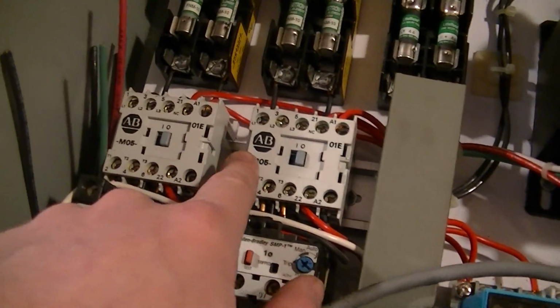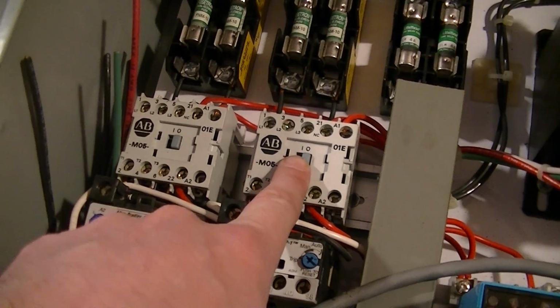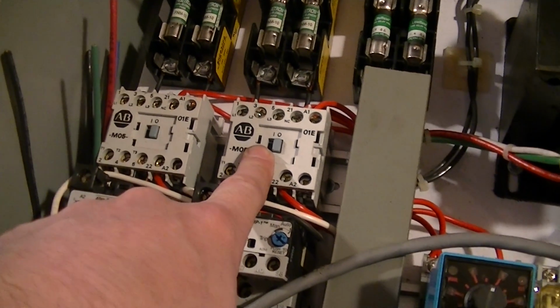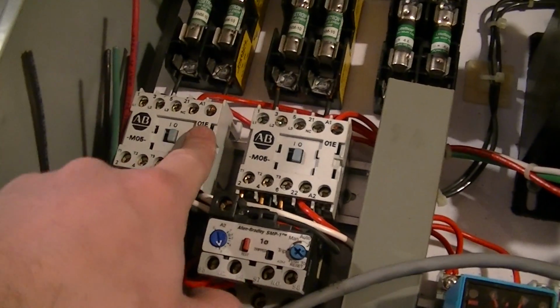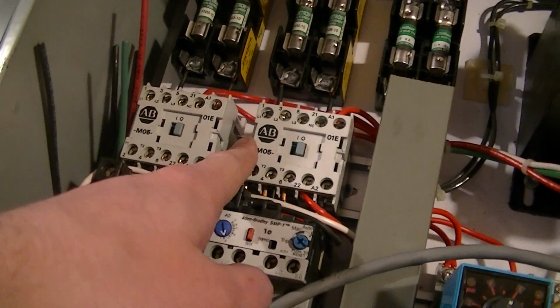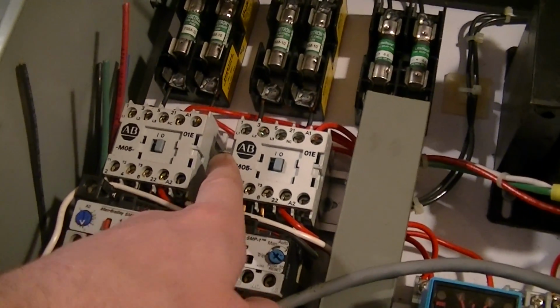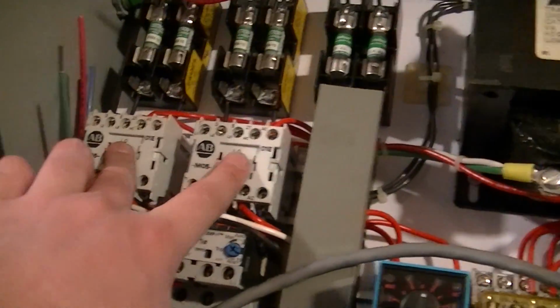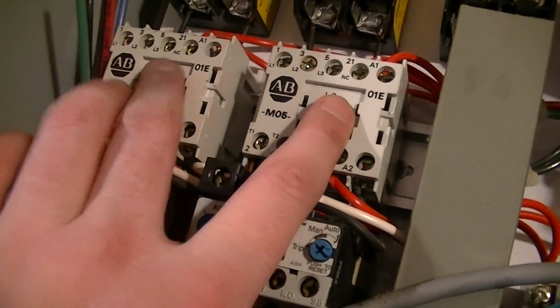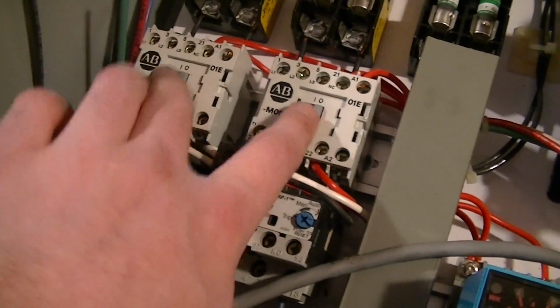So yeah, that's why it's got the control transformer in here, because it's got a number of relays and contactors. The difference between a contactor and a relay, of course, being that a contactor is a relay that's intended for really high operating currents. For example, these are fairly small, only a few hundred volts, most likely in the 10 to 20 ampere range, whereas you can get much bigger contactors like this guy.